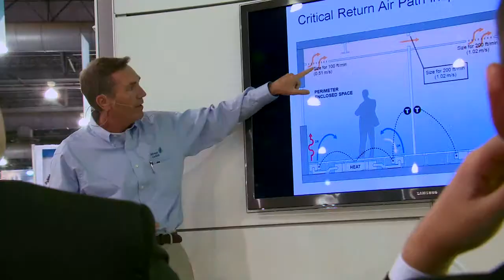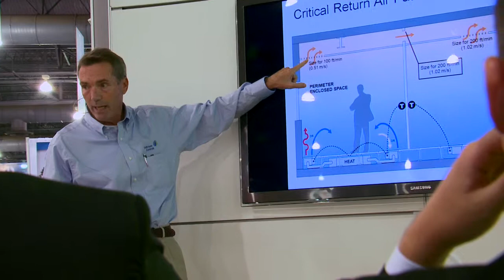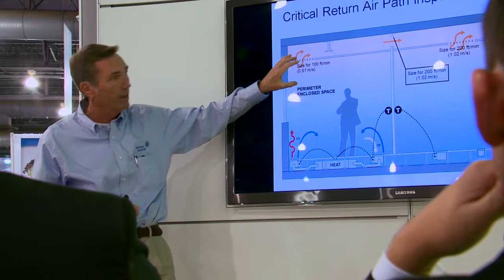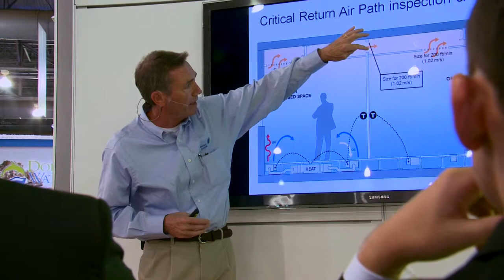These are some rules of thumb we typically size for now: no more than about 100 feet a minute velocity here, larger than you're used to. You're probably used to more like 400 or 500. At my cross grills, I'm looking at maybe 200 feet at the ceiling over here, and maybe 500 back at the shaft—basically larger return air paths.